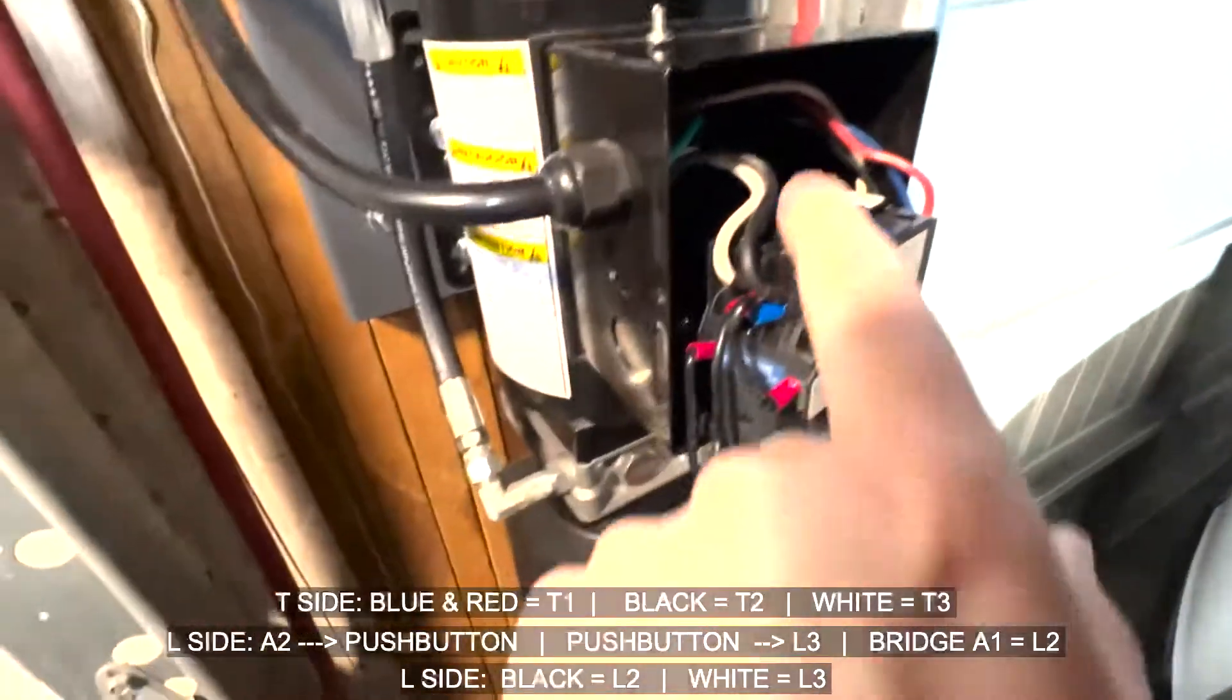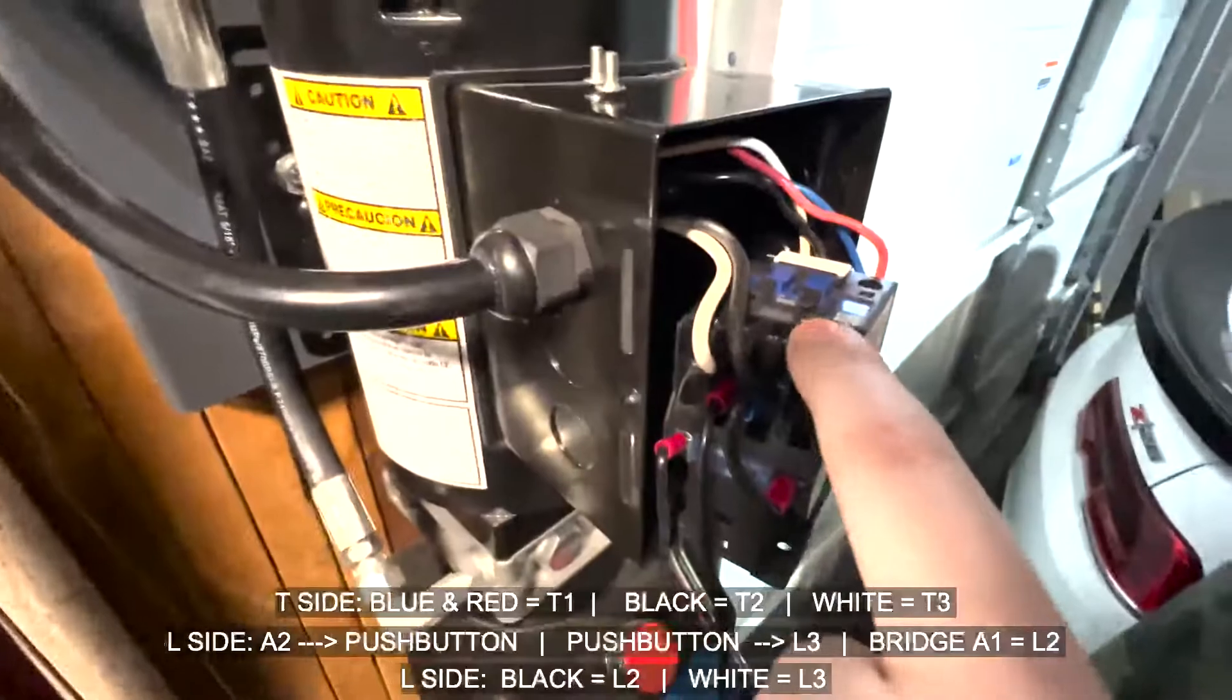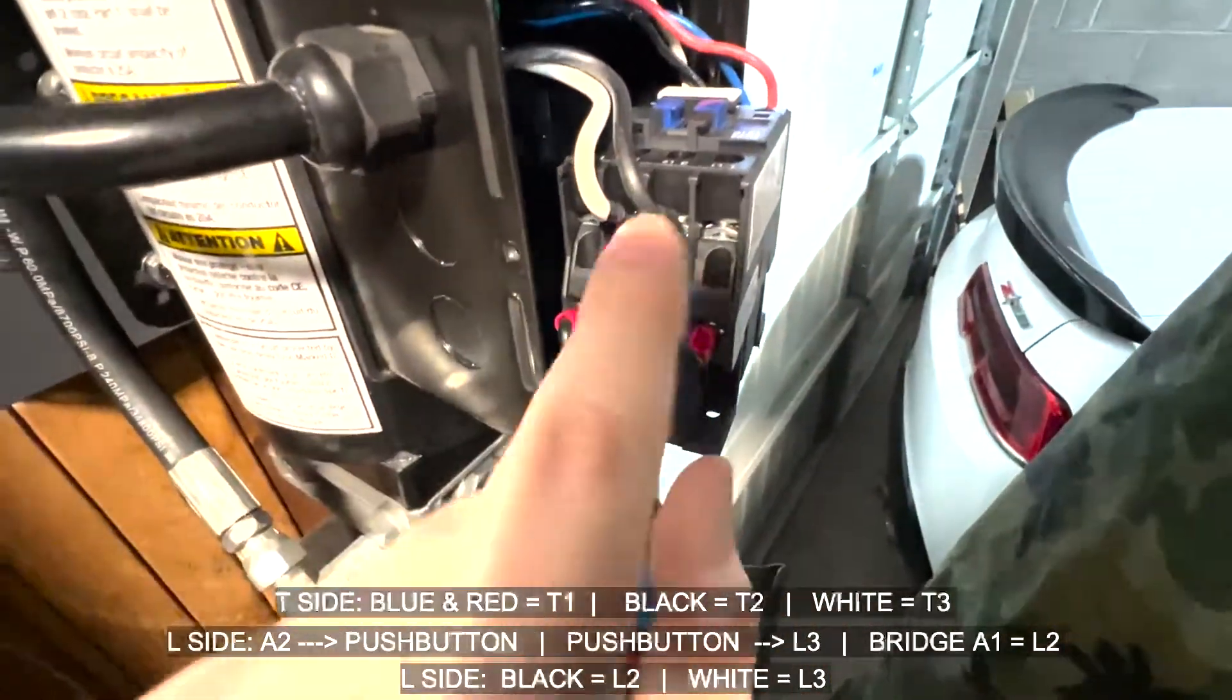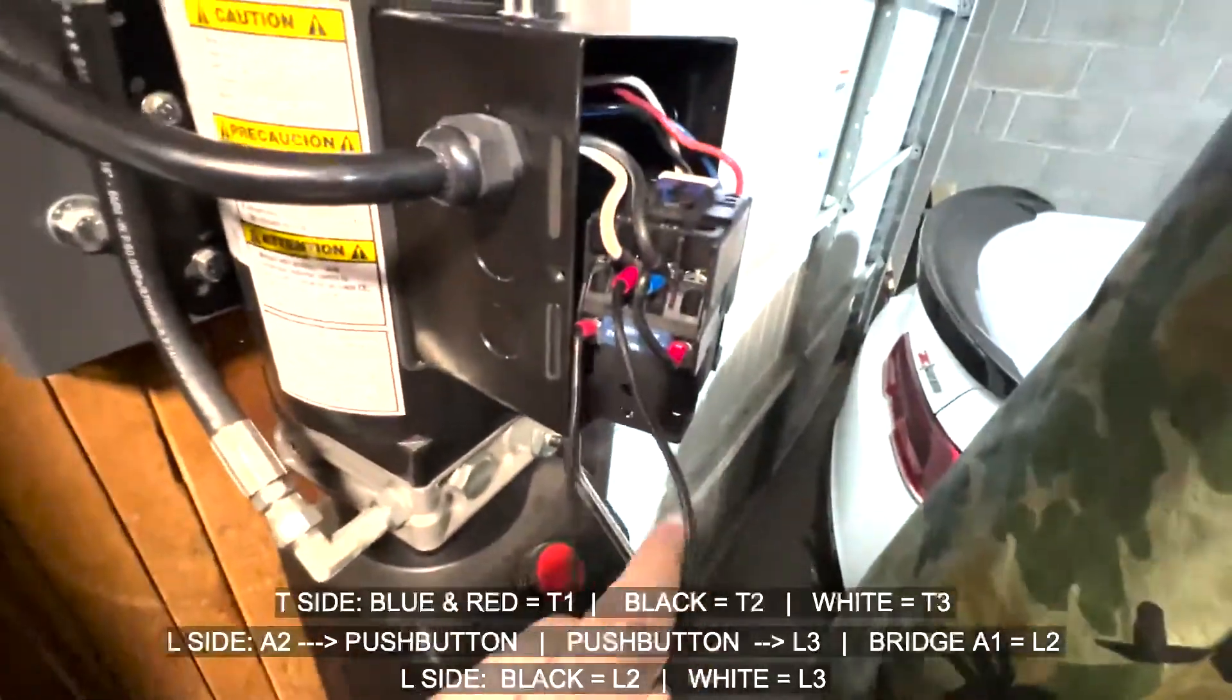It doesn't matter which hot you put. They're both the same. They're both just 220 or 110 power each. You're going to plug those in. Then you're going to have a bridge from your L2 come down to A1, pretty much just like that. And then you're going to have one from L3, which is right here, come into your push button on either side. I don't think it matters. Now don't hold me to that, but I'm pretty sure it does not matter. And then have the other side of your push button come out from here to A2.